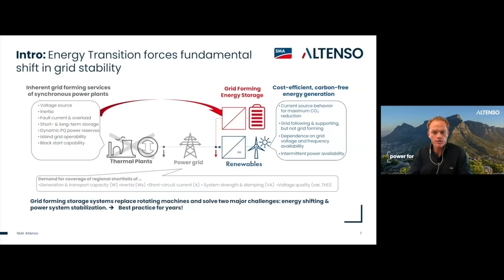So I just want to spend a minute to talk about grid forming technology and why this is a buzzword in the BESS landscape at the moment, because it ties into one of the solutions that I'll be talking about later on. So essentially, grid forming technology refers to power electronic systems that can actively establish and regulate grid voltage and frequency. And this is in contrast to your traditional grid following inverters, which have been used in the majority of renewable energy projects in the past, in the sense that they simply follow an existing grid signal and would trip in the case of a blackout or a grid fault.